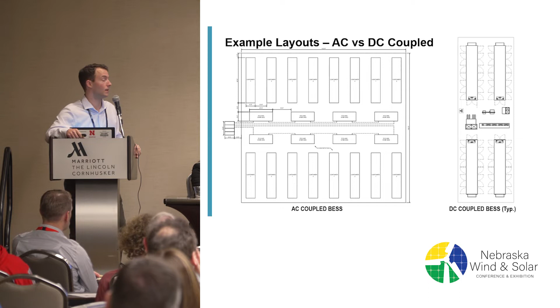From a layout and design perspective, one thing to think about with DC coupled is that when you situate your batteries and pair them with the solar inverters, those solar inverters are scattered throughout the site. So you'll have groupings of batteries also scattered throughout the site. Your energy density - the amount of land required for the battery - is impacted by that. You can't locate everything close to the substation with a DC coupled system.